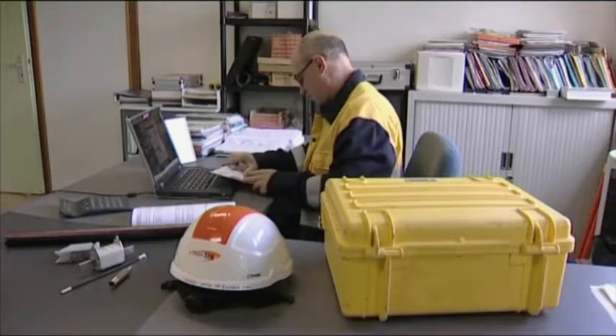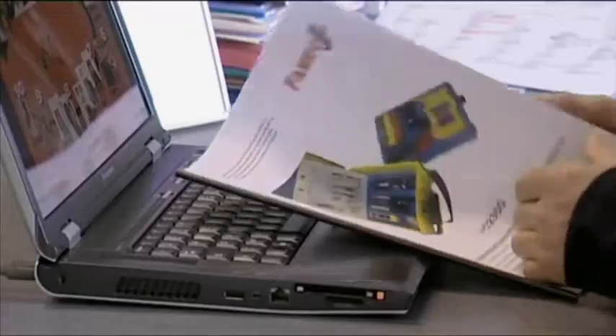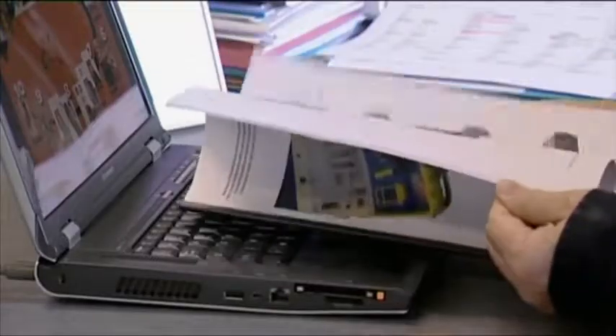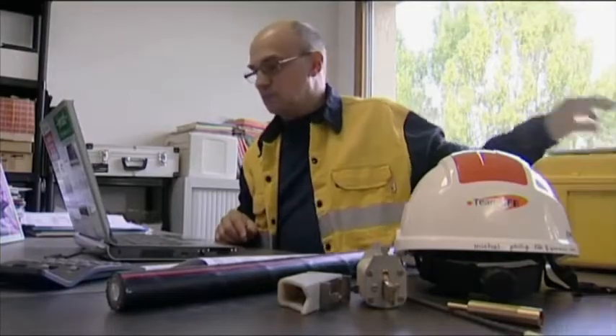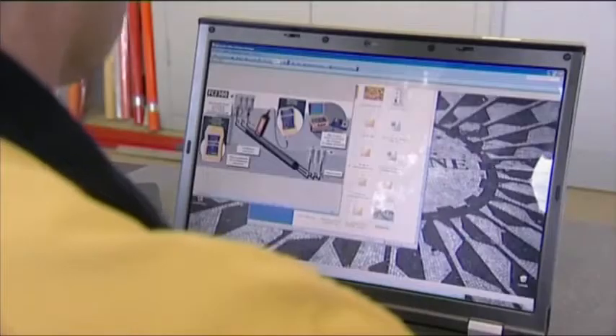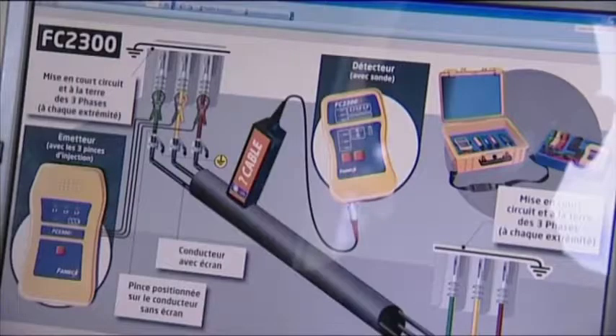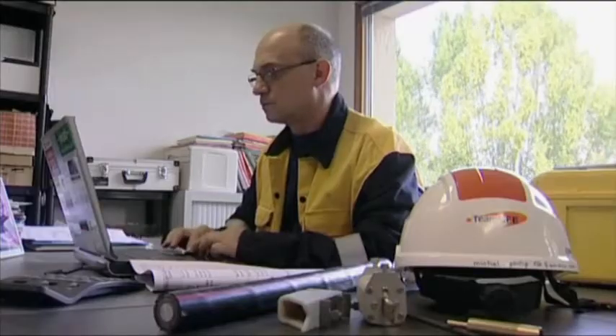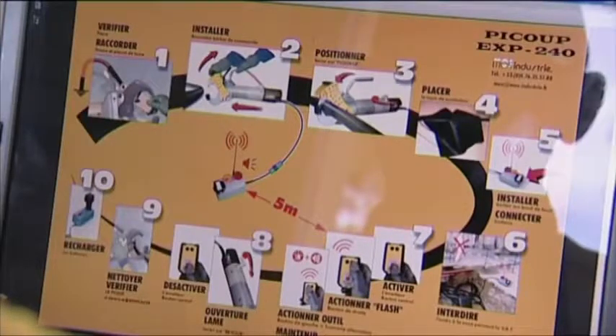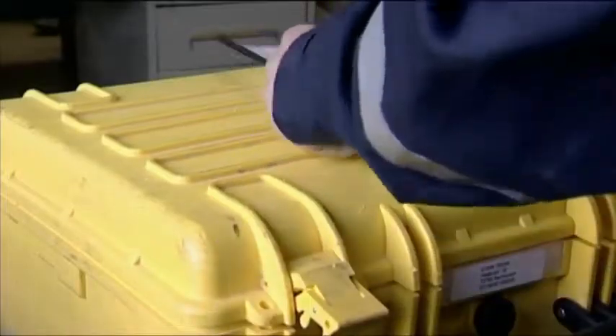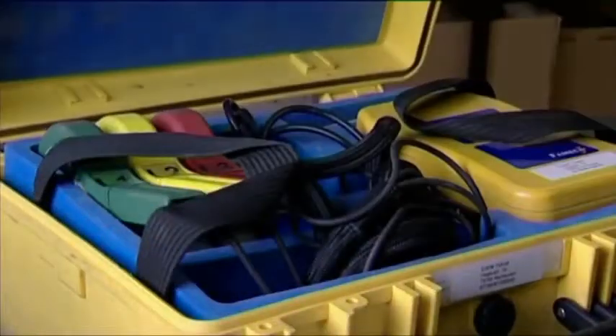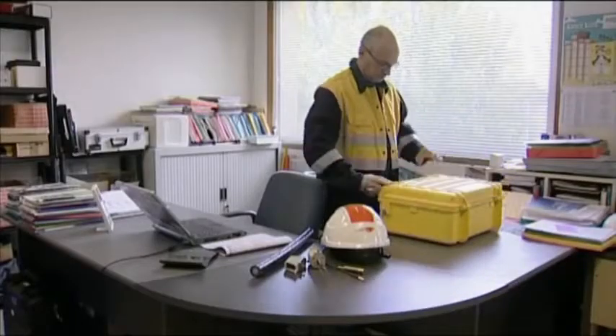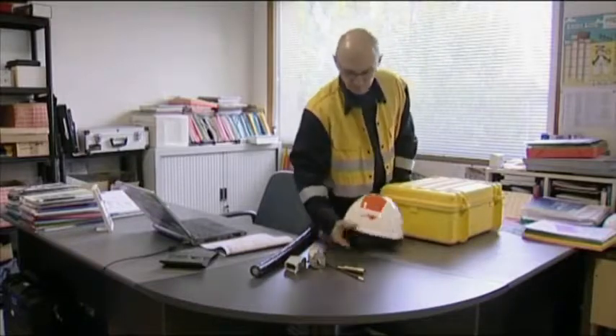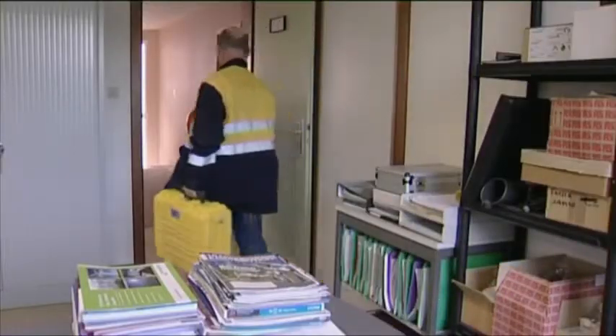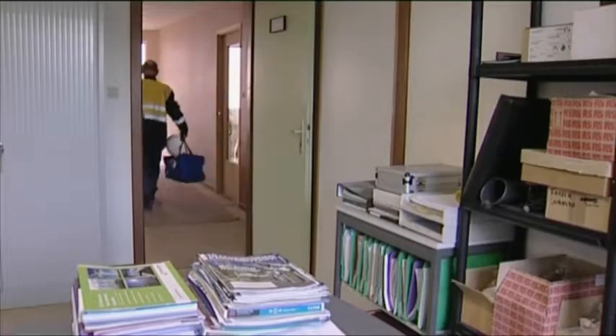When connecting a new substation, for instance, the electricians have to work within the framework of a safety procedure. This procedure, known as disconnection, complies with NFC 18510 standards. For underground networks, cable identification on the spot is the third stage of the disconnection procedure. It requires pre-identification, use of a spiking tool, cable cutting, as well as testing for electrical continuity. This sequence is specific to underground networks and is also referred to as secure identification.